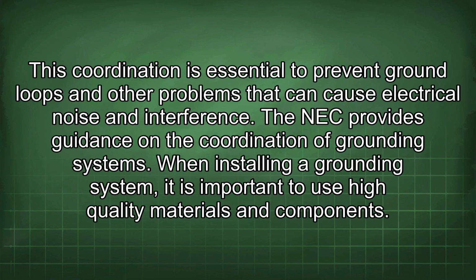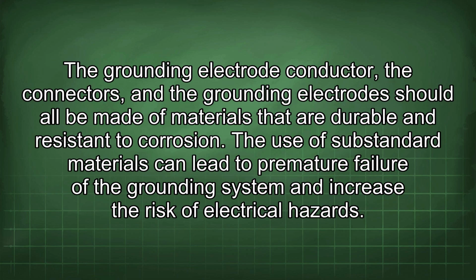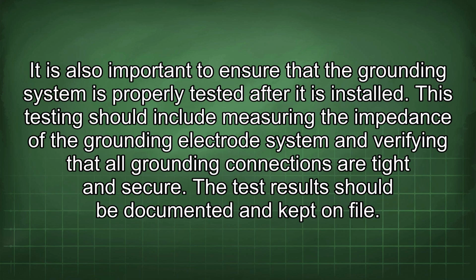When installing a grounding system, it is important to use high-quality materials and components. The grounding electrode conductor, the connectors, and the grounding electrode should all be made of materials that are durable and resistant to corrosion. The use of substandard materials can lead to premature failure of the grounding system and increase the risk of electrical hazards. It is also important to ensure that the grounding system is properly tested after it is installed. This testing should include measuring the impedance of the grounding electrode system and verifying that all grounding connections are tight and secure. The test results should be documented and kept on file.